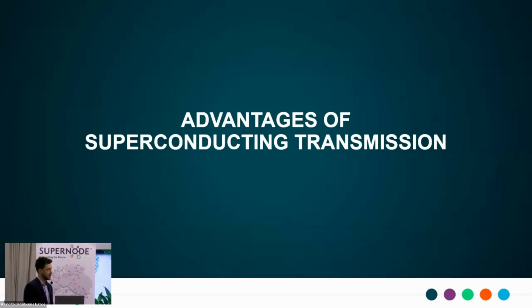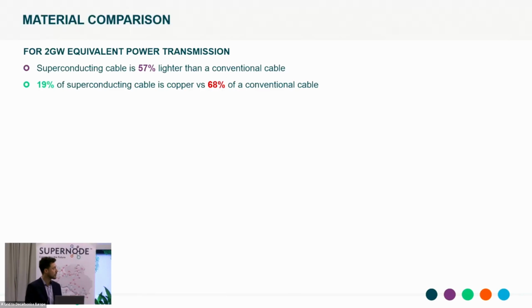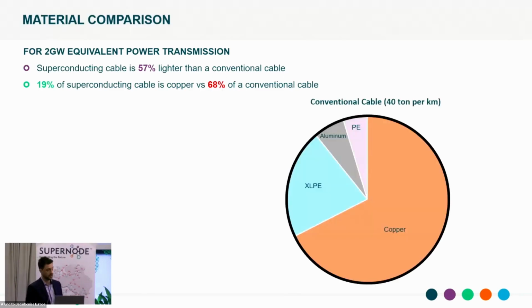At a high level, some of the advantages of superconductivity in transmission. First, we look at a material comparison - this is a cross-section of a typical 2 gigawatt power cable. As you can see, it's mainly copper, which is kind of what you'd expect - copper and electrical insulation, XLPE. It weighs about 40 tons per kilometer.